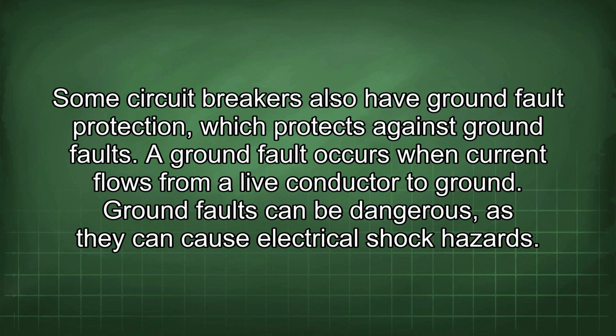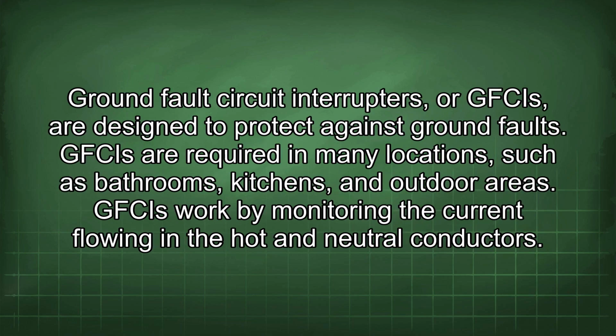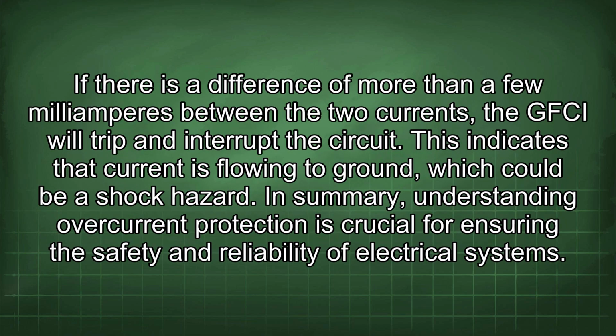A ground fault occurs when current flows from a live conductor to ground. Ground faults can be dangerous, as they can cause electrical shock hazards. Ground fault circuit interrupters, or GFCIs, are designed to protect against ground faults. GFCIs are required in many locations, such as bathrooms, kitchens, and outdoor areas. GFCIs work by monitoring the current flowing in the hot and neutral conductors. If there is a difference of more than a few milliamperes between the two currents, the GFCI will trip and interrupt the circuit. This indicates that current is flowing to ground, which could be a shock hazard.